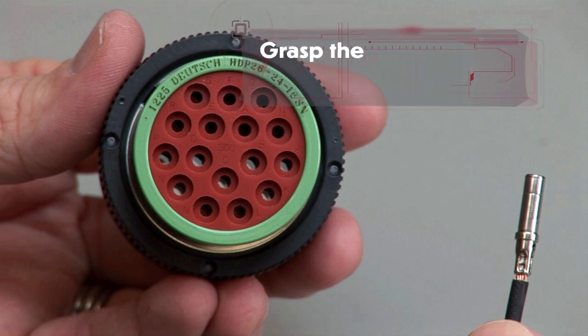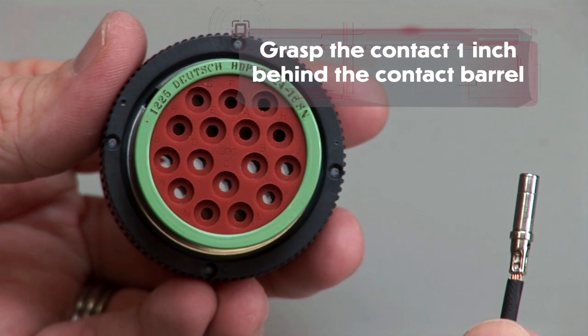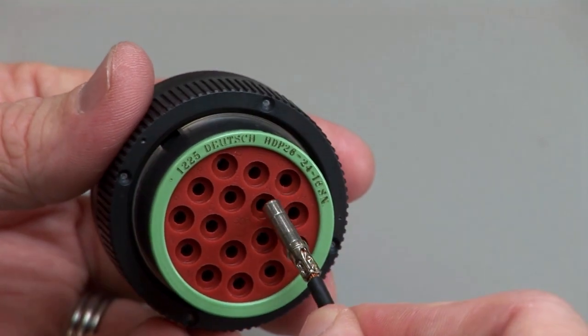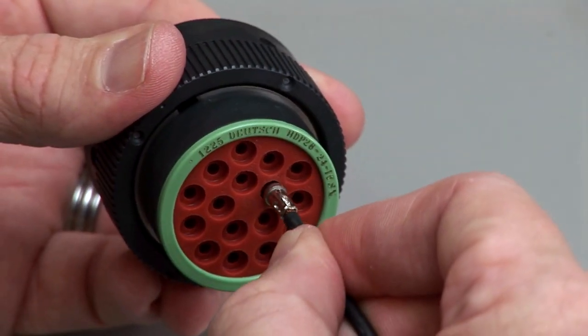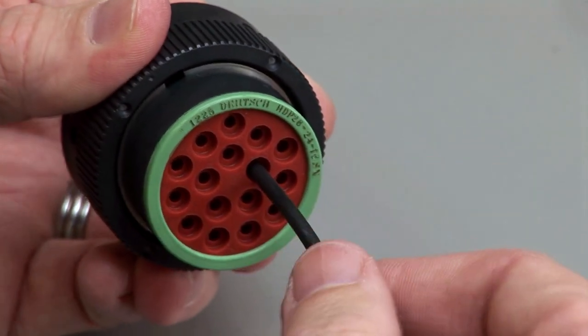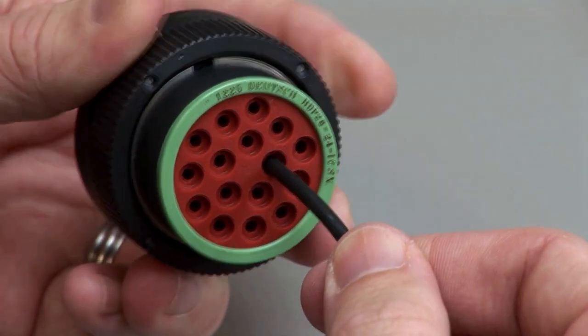Grasp the crimped contact approximately one inch behind the contact barrel. Hold the connector with the rear grommet facing you. Push the contact straight into the rear grommet until you hear and feel a click. A slight tug will confirm that the contact is properly locked into place.